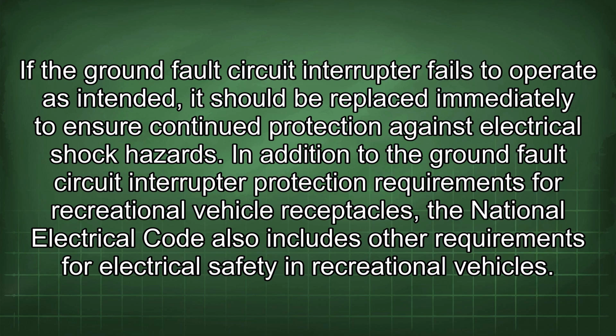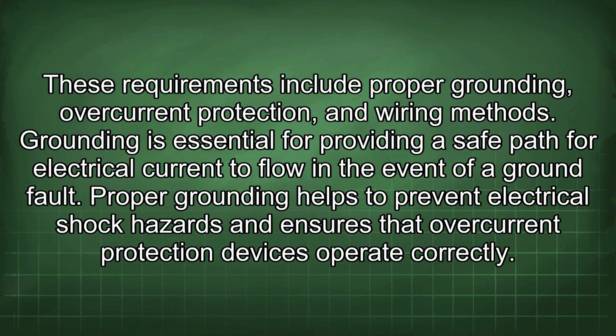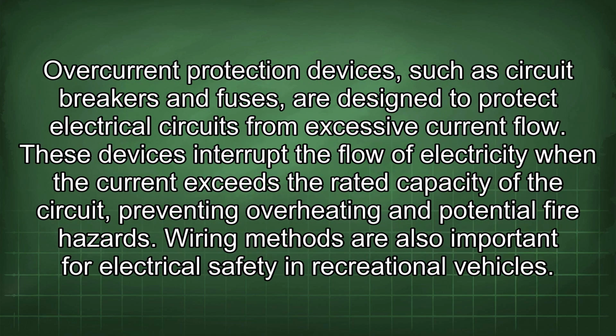In addition to the ground fault circuit interrupter protection requirements for recreational vehicle receptacles, the National Electrical Code also includes other requirements for electrical safety in recreational vehicles. These requirements include proper grounding, overcurrent protection, and wiring method. Grounding is essential for providing a safe path for electrical current to flow in the event of a ground fault. Proper grounding helps to prevent electrical shock hazards and ensures that overcurrent protection devices operate correctly. Overcurrent protection devices, such as circuit breakers and fuses, are designed to protect electrical circuits from excessive current flow. These devices interrupt the flow of electricity when the current exceeds the rated capacity of the circuit, preventing overheating and potential fire hazards. Wiring methods are also important for electrical safety in recreational vehicles.